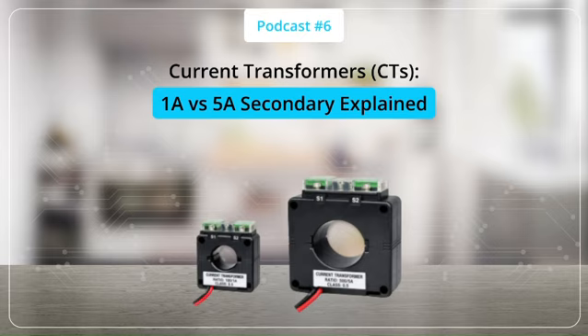When current flows through the primary conductor, it creates a magnetic field. This magnetic field induces a proportional current in the secondary winding. For example, in a 1,000 to 5 ratio, a 1,000 ampere current is reduced to 5 amperes in the secondary circuit. In simple terms, it works like a gearbox that reduces a high input into a controlled output that instruments can safely read.